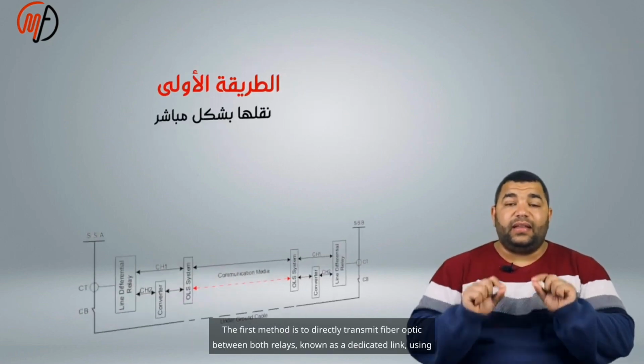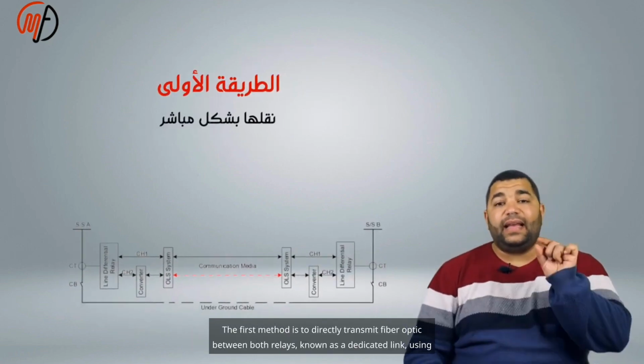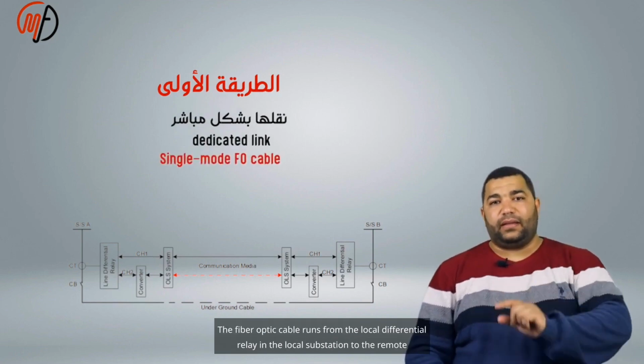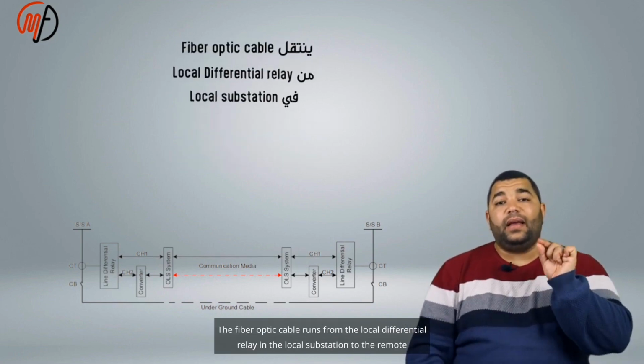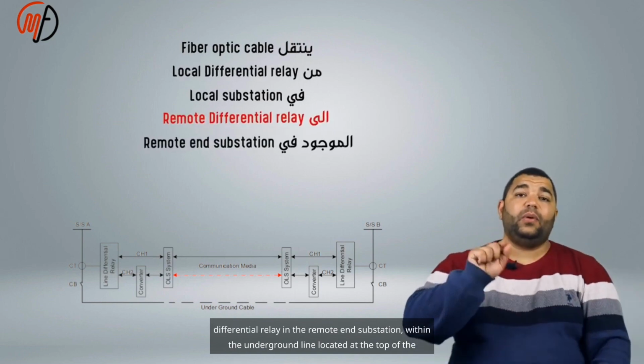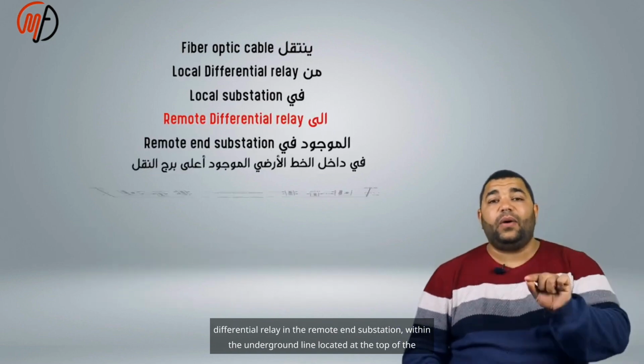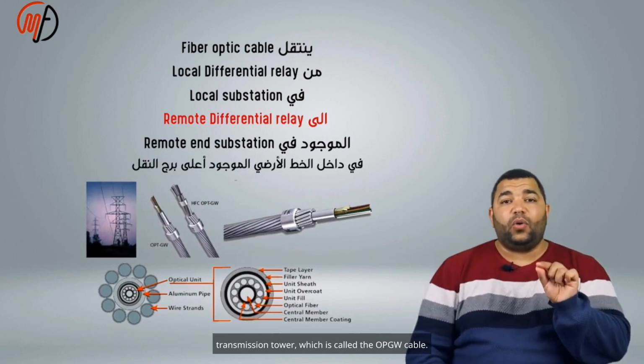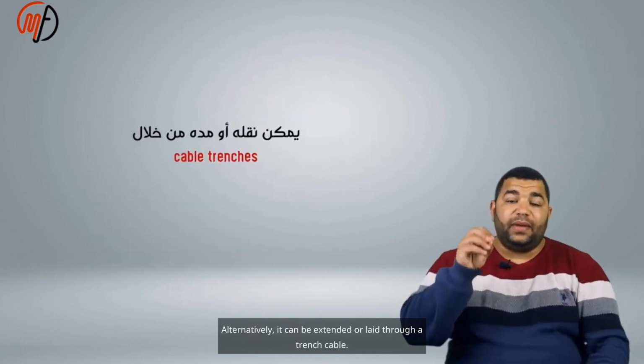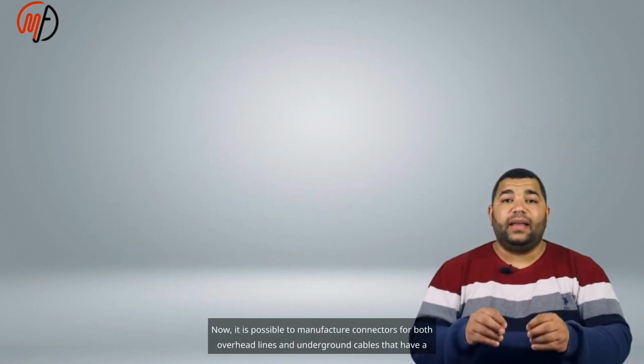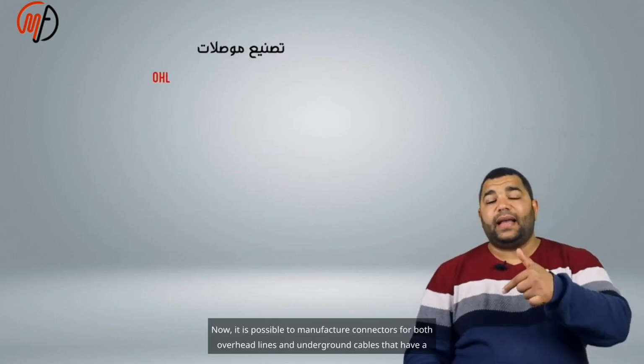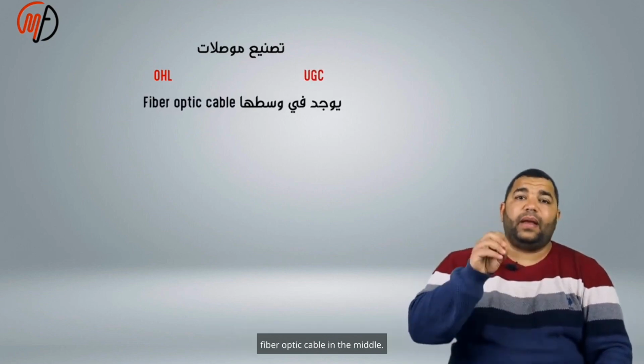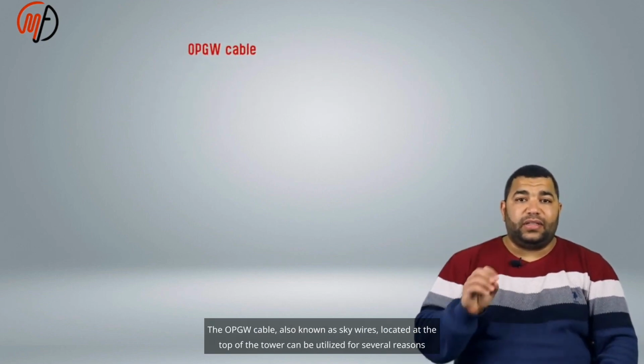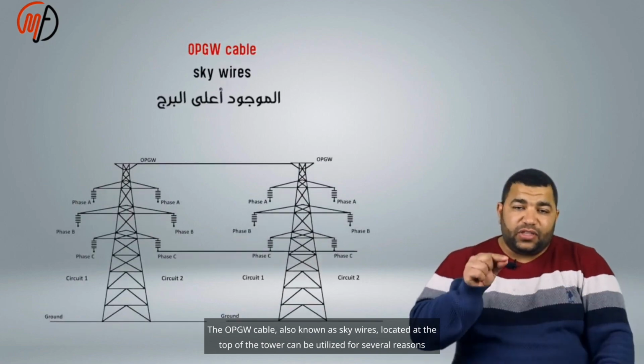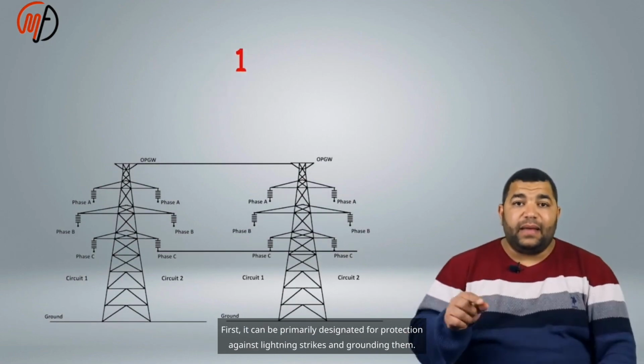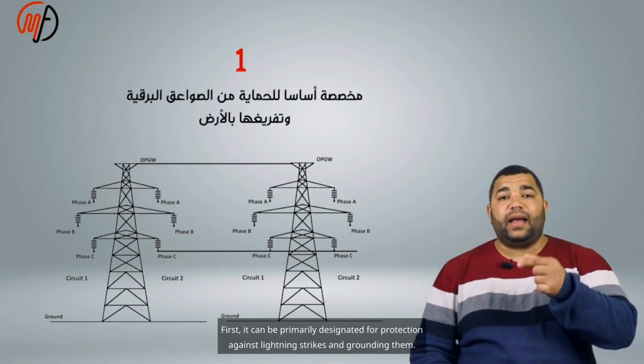The first method is to directly transmit fiber optic between both relays, known as a dedicated link, using single-mode fiber optic. The fiber optic cable runs from the local differential relay in the local substation to the remote differential relay in the remote end substation within the ground wire located at the top of the transmission tower, which is called the OPGW cable. Alternatively, it can be extended or laid through a trench cable. Now, it is possible to manufacture connectors for both overhead lines and underground cables that have a fiber optic cable in the middle. The OPGW cable, also known as sky wires, located at the top of the tower, can be utilized for several reasons. First, it can be primarily designated for protection against lightning strikes and grounding them.